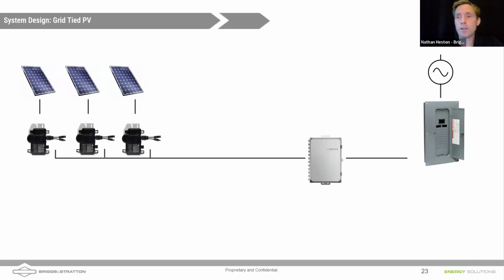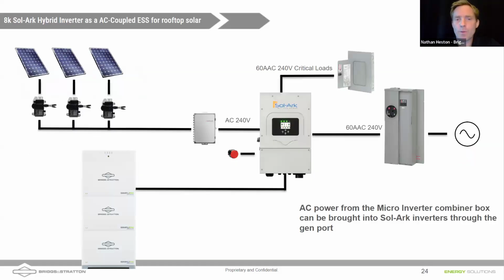We've lost net metering out here. Daniel, you do a really nice talk on NEM 3.0, which is very much not NEM 3.0, right? It's not net energy metering anymore in California. It's net billing tariff. And so financially it is no longer advantageous to do this kind of a system in many locations, not just California. If that customer wants backup power, if they want batteries, or if their NEM status is expiring, you have this option to come in and AC couple the output of those microinverters to a battery.